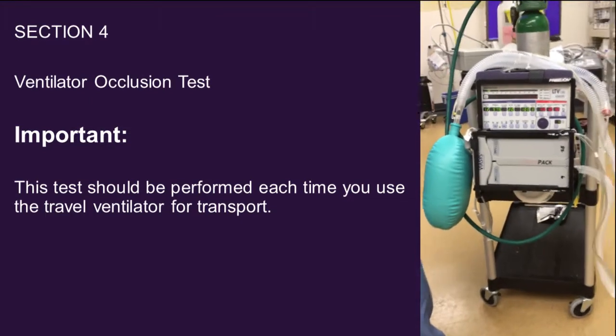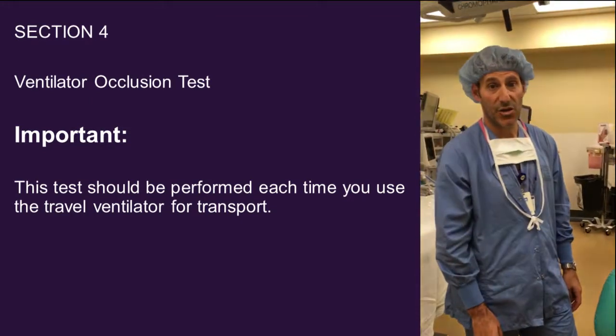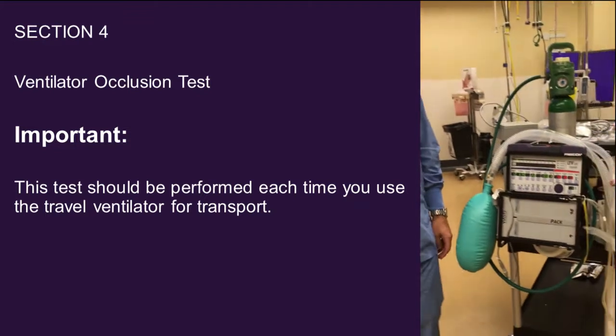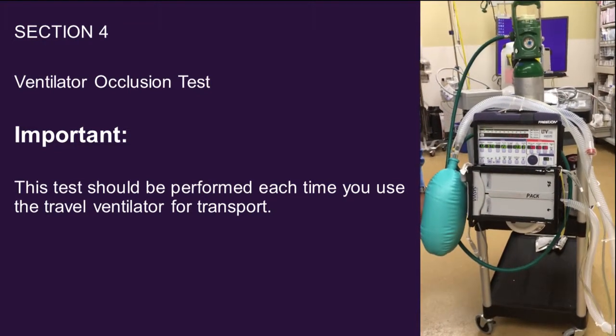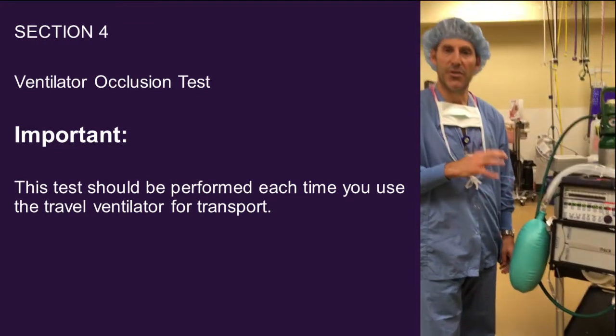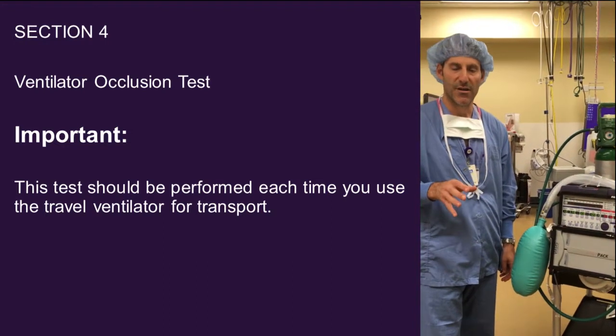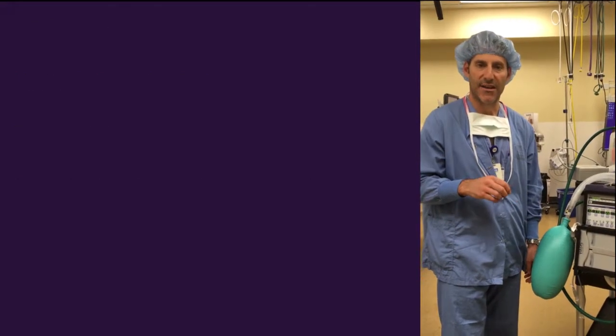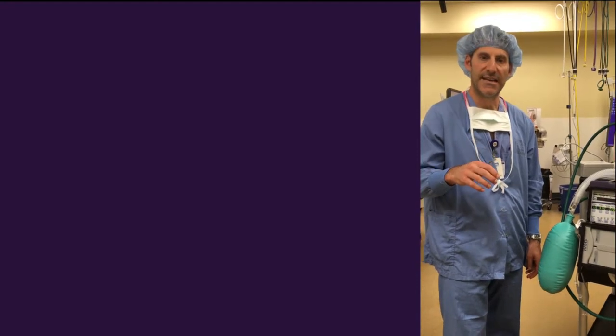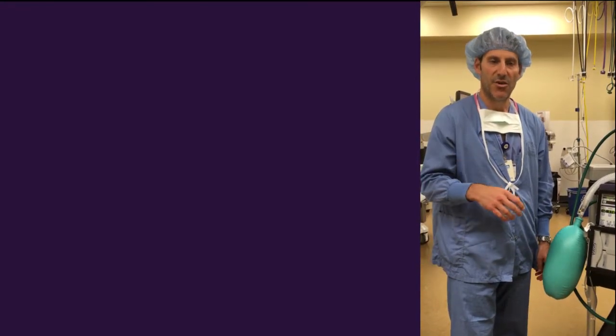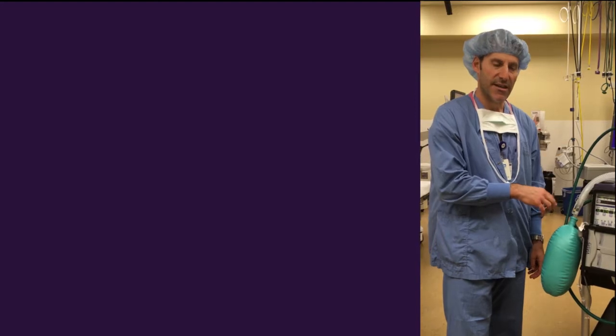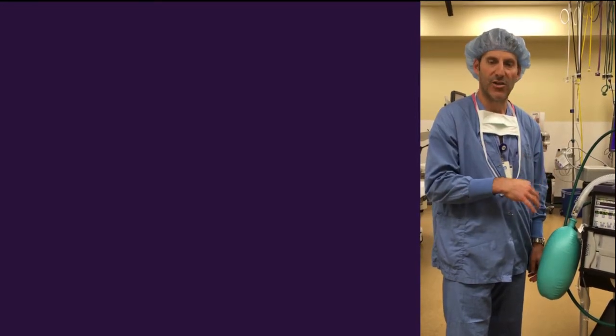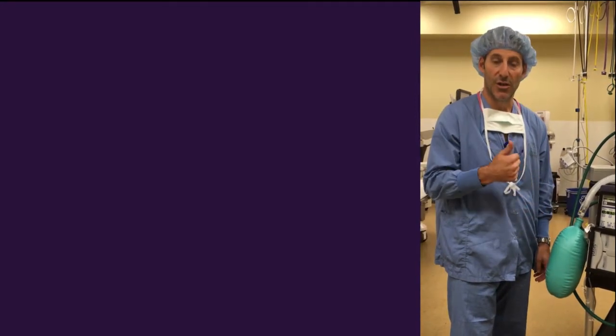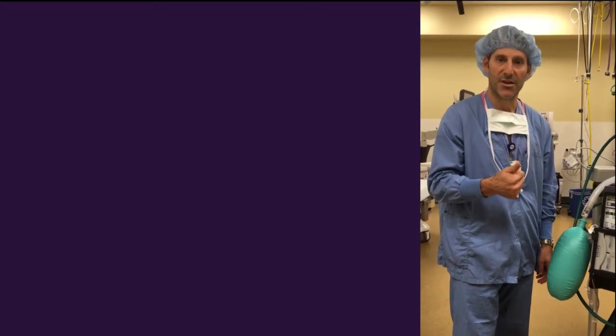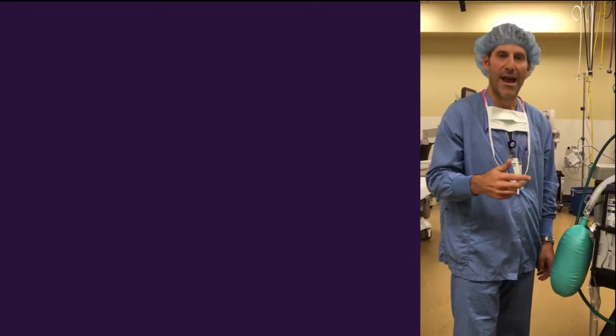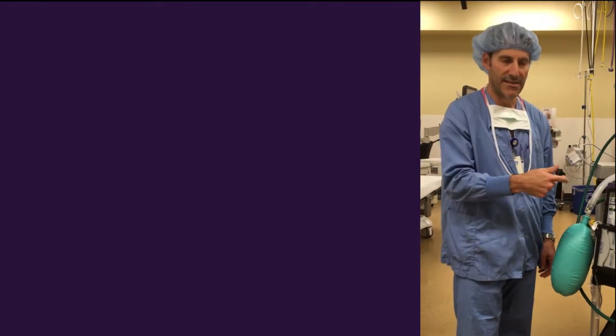What I'm going to demonstrate for you right now is called an occlusion test. It should be performed on the travel ventilator each time you go to use the travel ventilator for transport. The purpose of it is somewhat analogous to a positive pressure leak test on the anesthesia machine, insofar as that when the circuit is appropriately hooked up and completely occluded, the ventilator should alarm because of a high pressure and cycle without having given the volume that is set in.